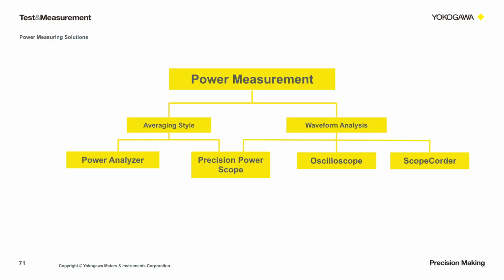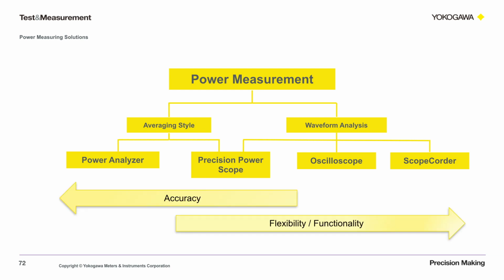So now we know the trade-offs for making voltage and current measurements. Now we need to decide what instruments we are hooking these up to. We categorize these instruments into averaging and waveform analysis. It's an important distinction between these instruments because they calculate power differently. In general terms, the trade-off of these instruments is the same as with the current measurements, really accuracy versus flexibility. On the accuracy side, you have the averaging style. On the flexibility side, you have the waveform analysis.